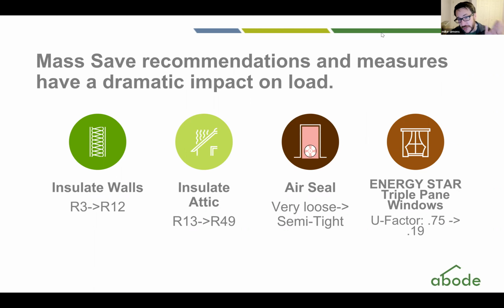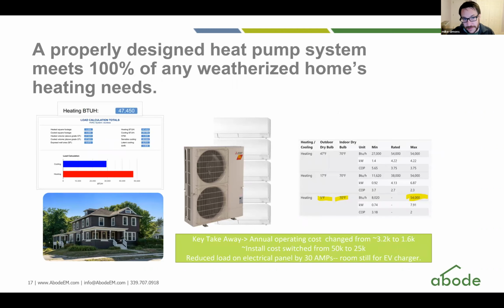But I took my uninsulated walls, I packed them full of insulation. I took my poorly insulated attic, I aligned the thermal barrier correctly, and I filled that with insulation. I tightened up wherever I could along the house, and I did things outside of what the Mass Save contractors would normally do. They also upgraded all of my non-architecturally important windows to high performance windows. And when I did all of those things, instead of needing a heat load of over 100,000 BTUs, my heat load fell to less than 50,000 BTUs. All of those improvements, insulating the walls, replacing the windows, properly insulating the attic, sealing up the home, cut the heat load in half, which is remarkable.